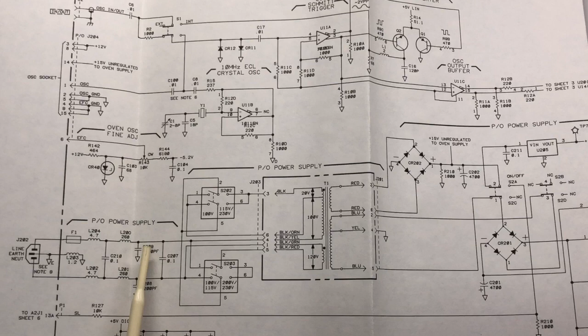These capacitors here that are the X class capacitors are self-extinguishing. So again, if they were to fail and short, they're self-extinguishing, so if they catch on fire, they will go out, and they're designed so that an external fuse will blow, but again, they fail in a safe way and contain the failure to that capacitor. So when you see capacitors, again, across the AC line or line to a chassis ground connection, they must be safety rated.